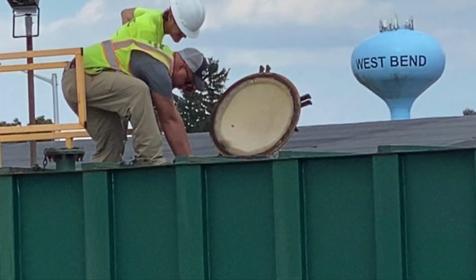You want to be careful with the air monitoring. When you open up a tank, there's flammable liquids in there, and you want to make sure that that's all ventilated out properly. So they'll go in with monitors and make sure that's all at acceptable levels. And then basically then the tank comes out, and again they monitor the atmosphere inside the tank and clean it out when it's safe to do it.